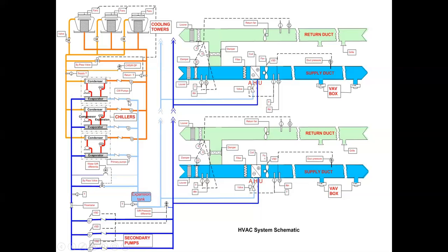So we've got our warm water coming back, 54. What's this little sideways Z about? Anybody ever seen one of those before? Is that a lazy Z wrench because it's laying on its side? That's a check valve. We'll talk more about this, but when you put in pumps, let's say you turn this pump off and you don't have a check valve. If this line over here is pressurized, you might allow water to flow backwards through the pump because the pump's off. A check valve doesn't allow water to flow backwards when you turn a pump off. It's a simple idea, but you can screw up some, think about it.